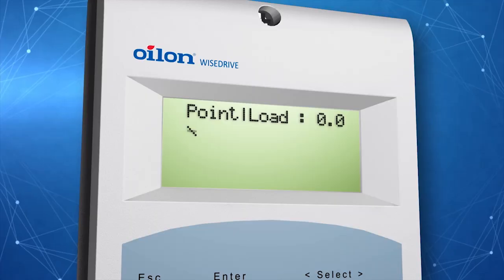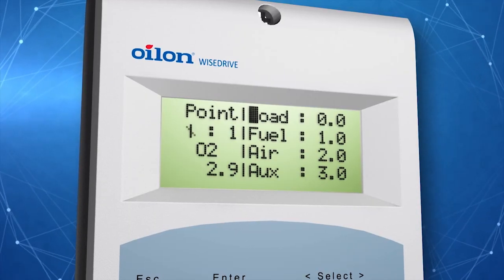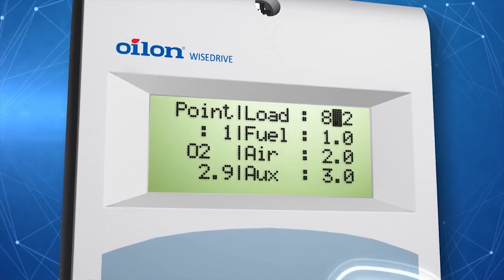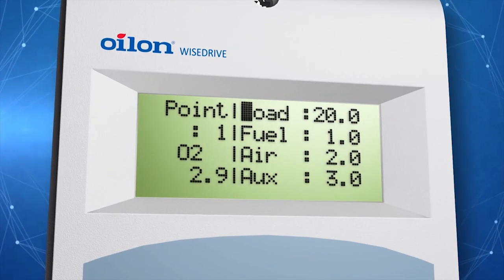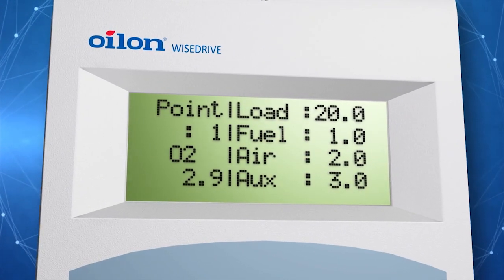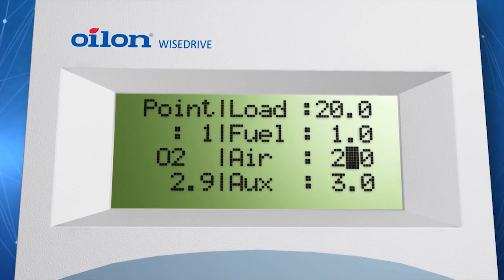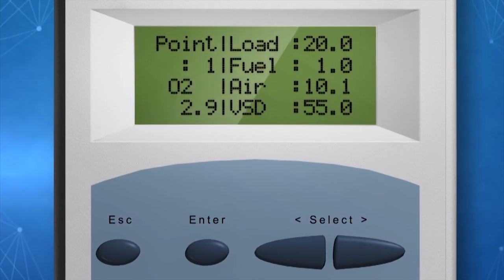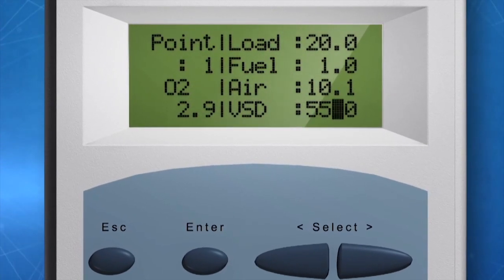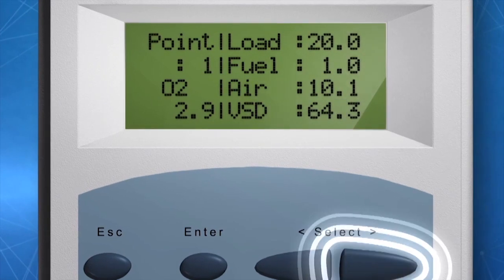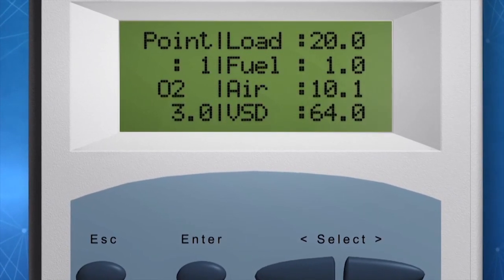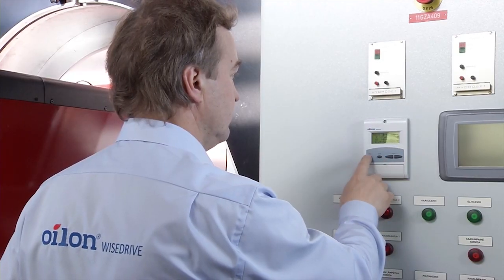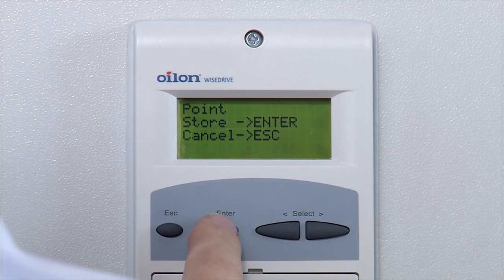The first point is the ignition point. After this, you can start adjusting the point data. Set the load value in percentage points to match the actual minimum load point. The oxygen level is shown on the display. When adjusting the point data, observe that oxygen is at a suitable level. After changing the values, wait until the changes take effect — that is, when the oxygen level does not change anymore. When all values are set and you want to save the point data, press escape. Then choose store by pressing enter.